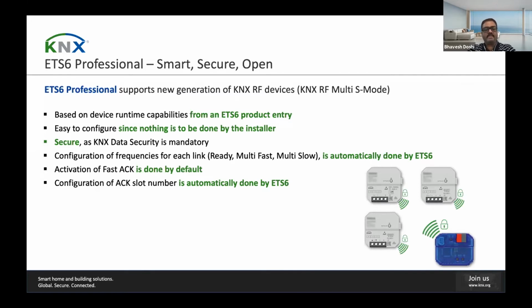So continuing with the system extensions that are supported in ETS6 Professional is the RF Multi, the new generation of RF devices. All in all, KNX RF Multi is about multiple radio frequencies between which the device may switch if one is blocked, and acknowledgement of telegrams. Moreover, they do have mandatory security support, easy configuration since all the frequency settings are automatically set by ETS, and of course, all the runtime capabilities come from a product entry created with the ETS manufacturer tool.